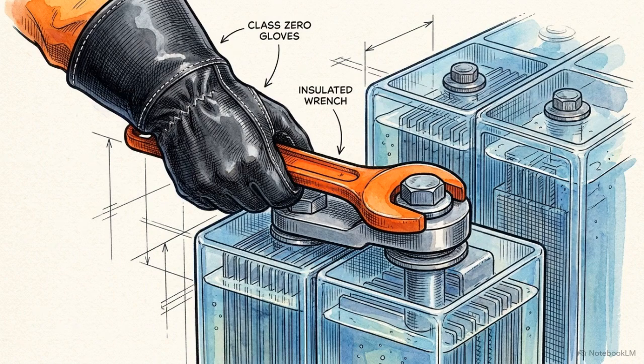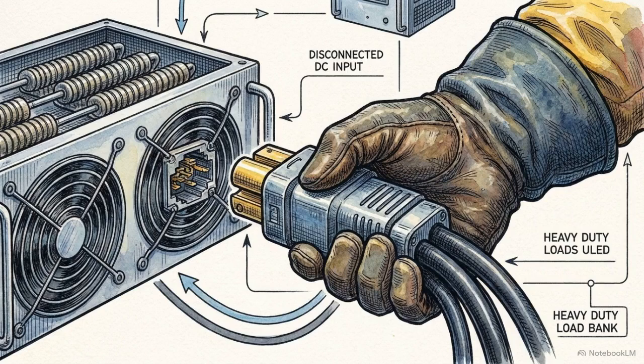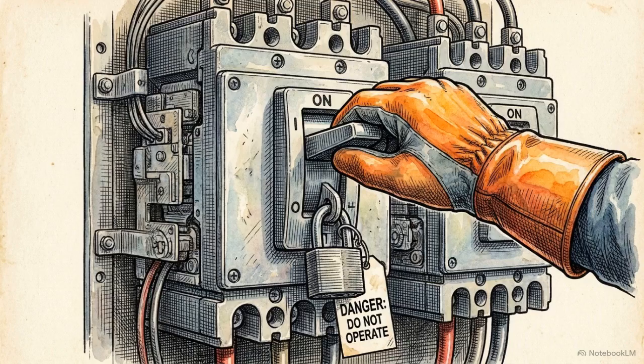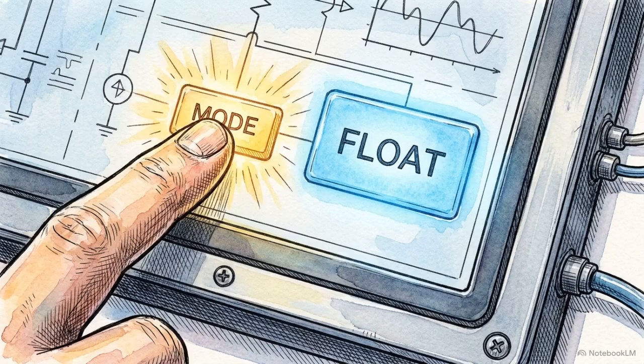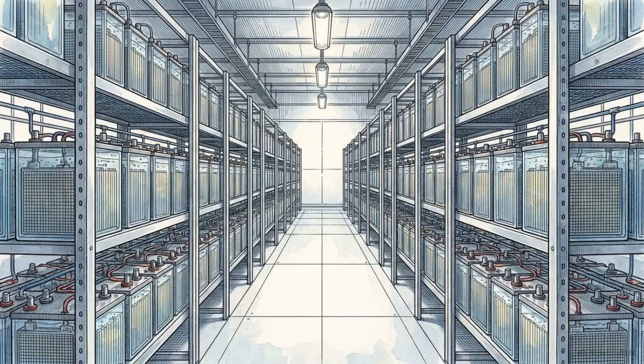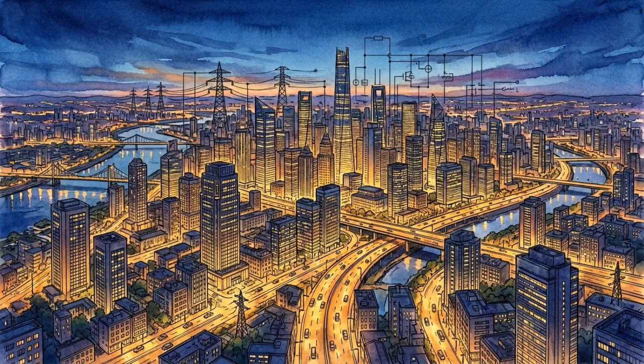Once everything passes, restoration begins. The mandatory first step is the physical removal of all temporary simulation links, ground faults, and external load banks. The main battery bank is then mechanically reconnected to the charger, and all tripped test alarms are manually reset. Finally, the entire DC system is returned to its approved normal float operating mode. Reaching this zero-alarm, fully restored state marks the end of the validation process, leaving the substation with a verified and operational power source.